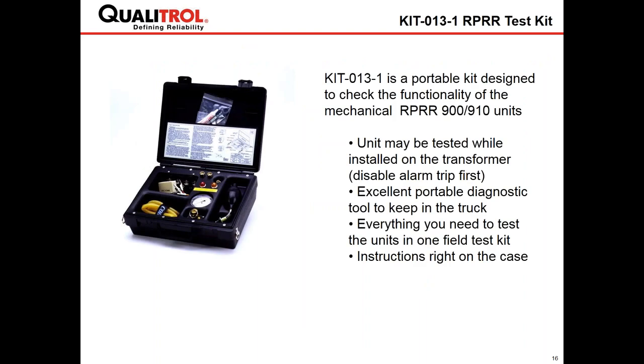First, we're going to cover kit 013, which is for the mechanical rapid pressure rise relays. So kit 013 is a portable kit designed to check the proper functionality of your rapid pressure rise relay, whether that's a 900, which is a unit that's used in oil space, or a 910, which is a unit used in gas space on your transformer. We've had this kit around for over 20 years, and we've had thousands being used around the globe. The units can be tested while installed on the transformer.